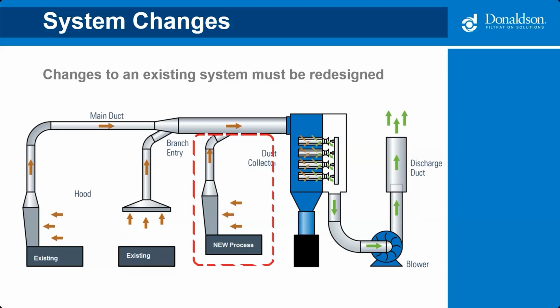And the reason I bring it up is we'll see sometimes where customers will want to add or remove a process to their dust collection system. And I've tried to highlight there with this little red box where now a new branch has been added to a new process in the factory. And what's very important to understand is the pressures in the system and the flow rates in the ductwork are all designed for your application. When you change that by either adding a process and adding ductwork or removing, the same is true as if you actually take a process away and plug off a branch, you've now changed how that whole system is going to flow and how it's going to work.